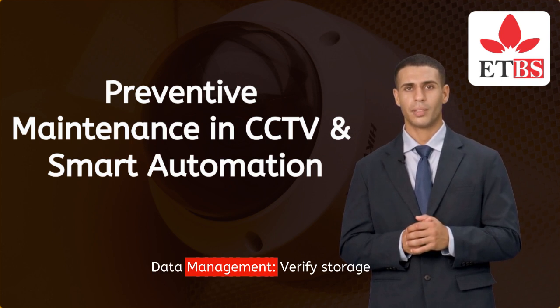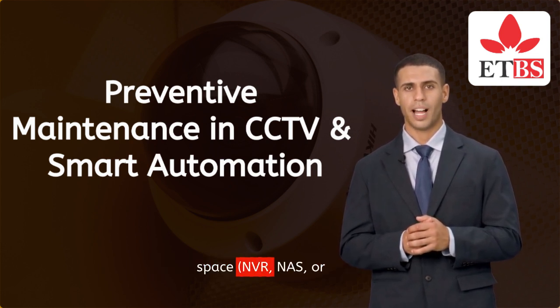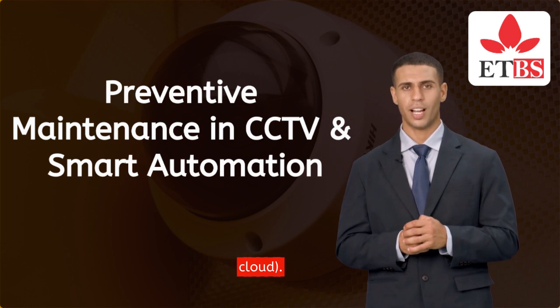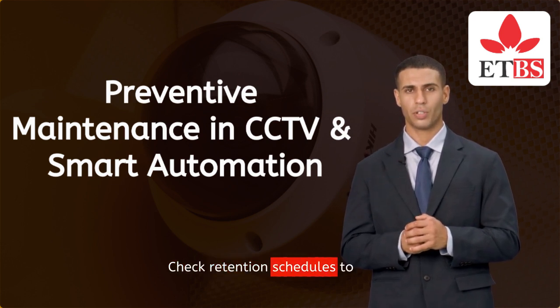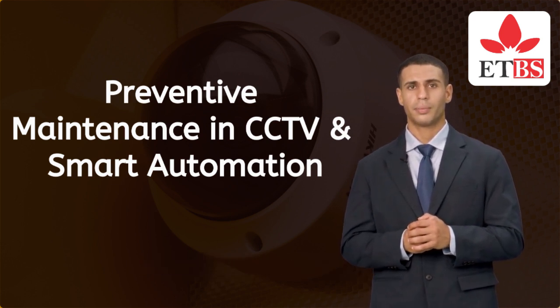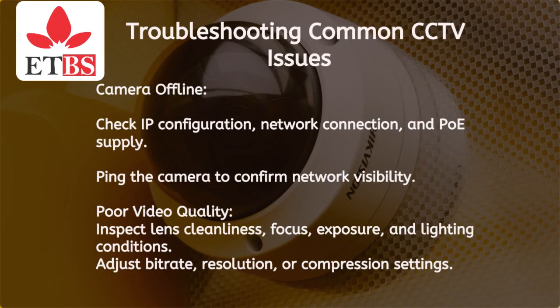Data management. Verify storage space, NVR, NAS, or cloud. Check retention schedules to ensure compliance with regulations. 2. Troubleshooting common CCTV issues. Camera offline. Check IP configuration, network connection, and PoE supply. Ping the camera to confirm network visibility.